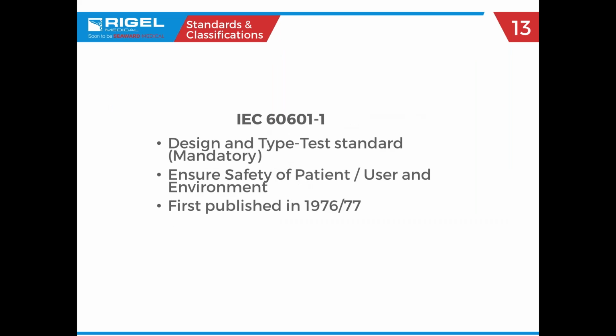Okay, so the 60601 standards. We talked a little earlier about these being the manufacturing standards within the industry, and about them being more stringent than some of the others. 60601 came around in 1976, basically to ensure the safety of both the patient and the user of the device. It is also done in single fault conditions such as open earth, to look at the increase in leakage current at that point. And then I believe it's also done in open neutral, where it's looking at the increase in the leakage current going on there. Once again, you're going to have to test the applied parts, or the patient connections.